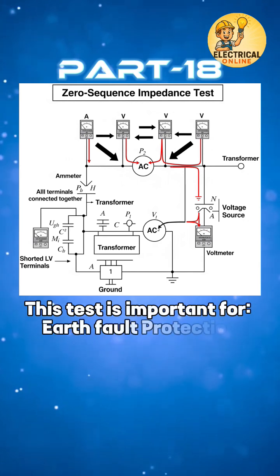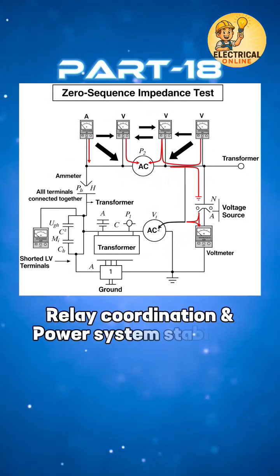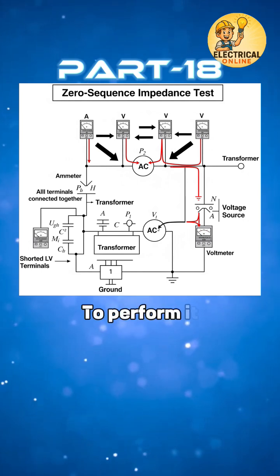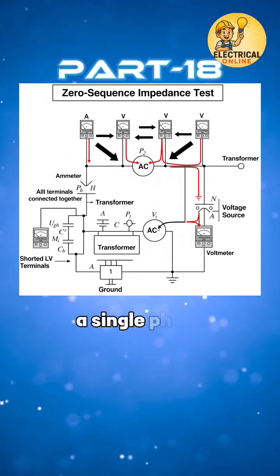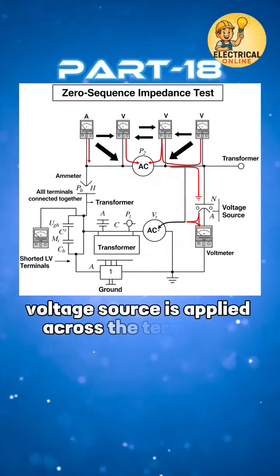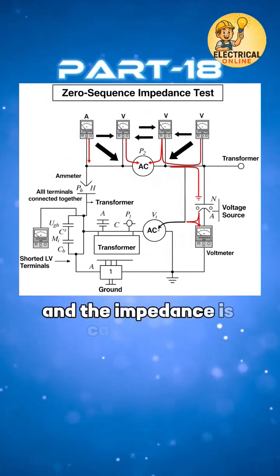This test is important for earth fault protection settings, relay coordination, and power system stability. To perform it, all three phase windings are connected in series. A single phase voltage source is applied across the terminals. The resulting current is measured, and the impedance is calculated.